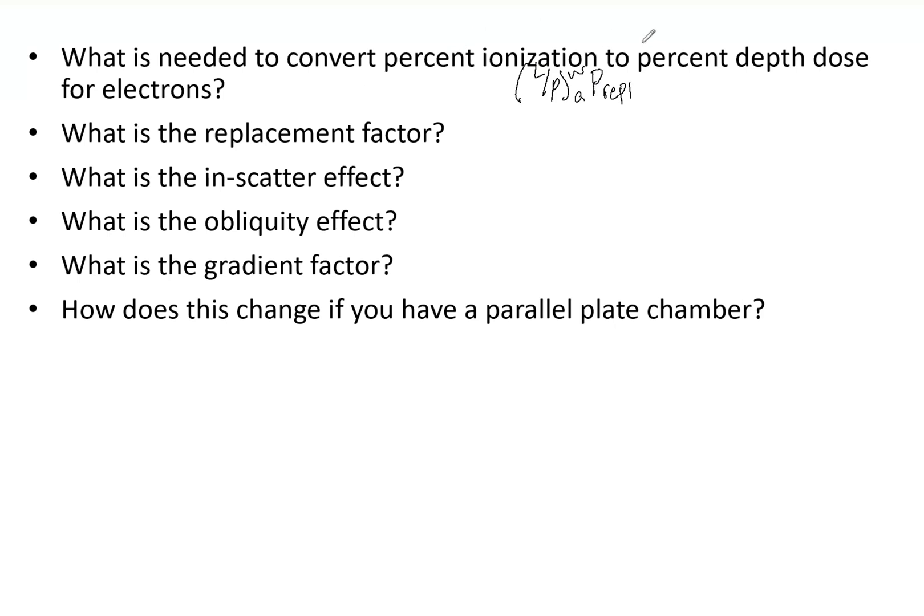We mentioned this P_replacement. So what is this? That is the chamber replacement factor which is dependent on the air cavity diameter and the mean electron energy. This accounts for in-scatter, obliquity, and the gradient factor, so it's multiple factors in one.